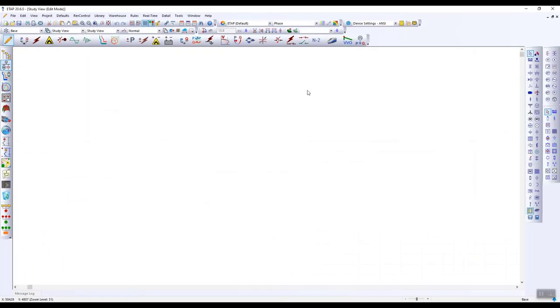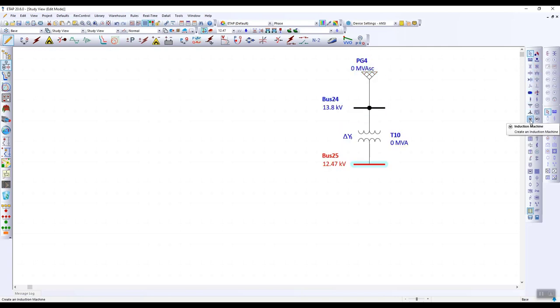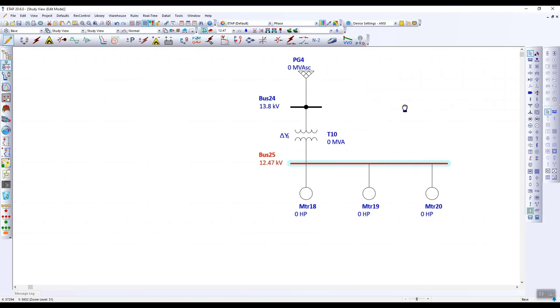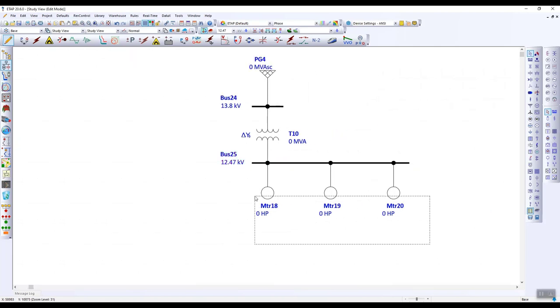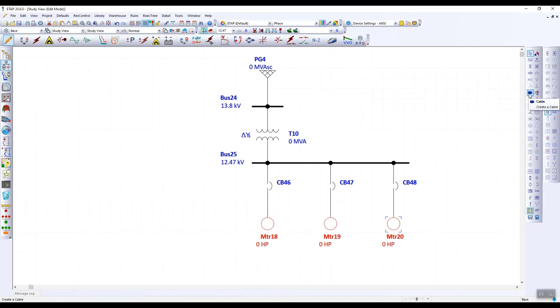To begin modeling in ETAP, I can enable auto build, which allows for equidistant spacing between my devices and only allows appropriate devices to be connected to each other. I'm going to start out by building a small model, and I can just click on the devices that I want to add into my single line diagram. I can quickly add as many motors as I'd like to this bus. I can add in my protective device, and I can add in my cable.